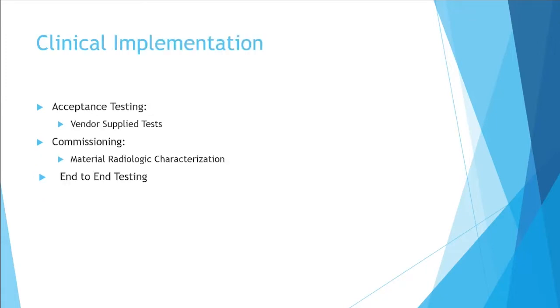Okay, so first off, talking about our clinical implementation, and this process was really separated into three separate areas. The first was acceptance testing. And this is very much akin to the acceptance testing you may do when you're accepting a new linear accelerator or other CT scanner equipment into your department. So this mostly included vendor supplied tests, which are testing the fidelity of the equipment and the ability of it to accurately print the bolus and make sure that it's functioning as expected.